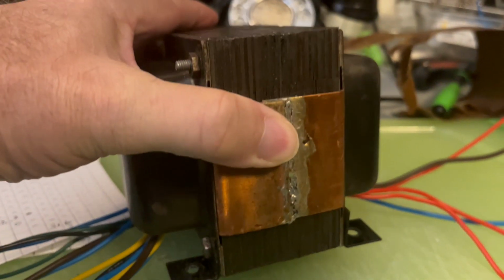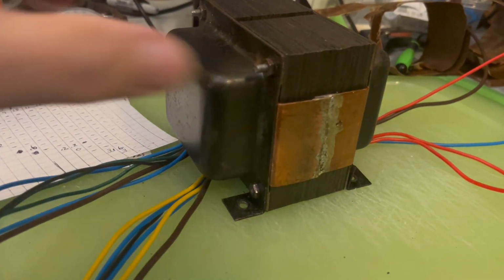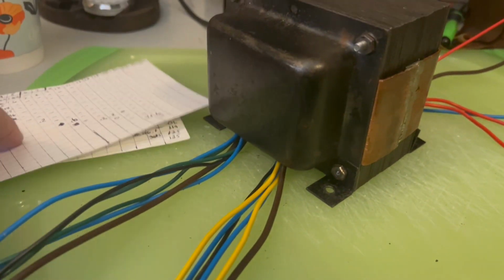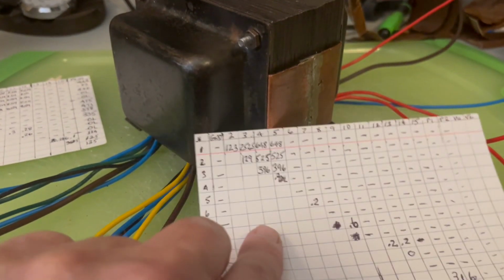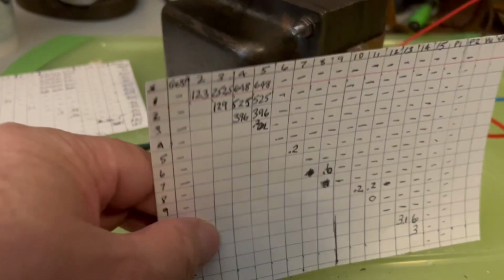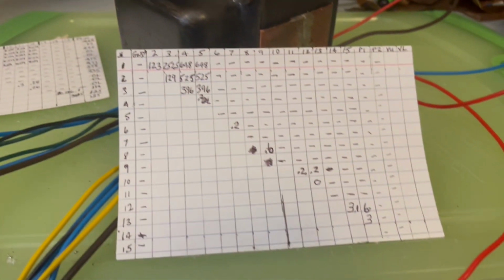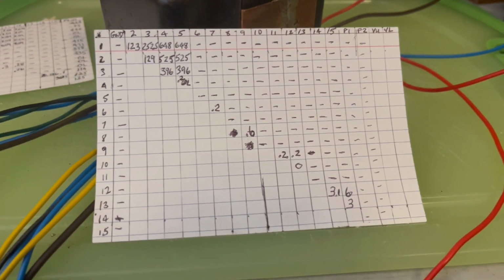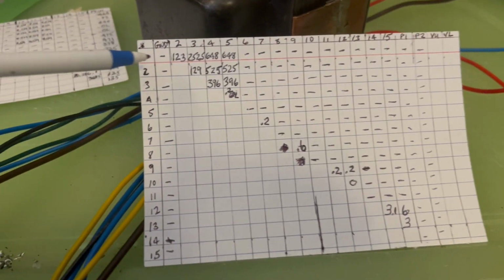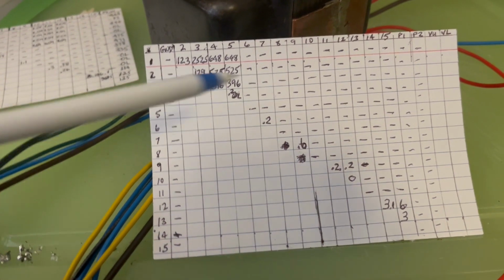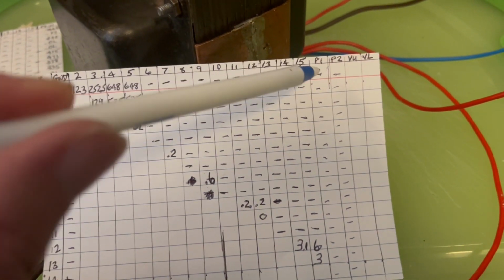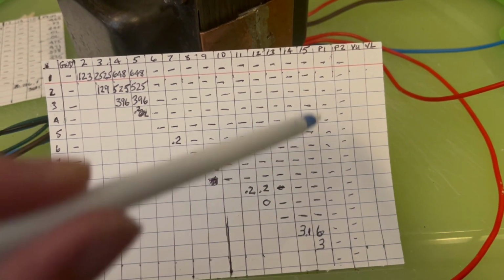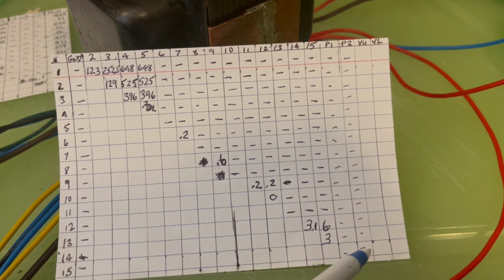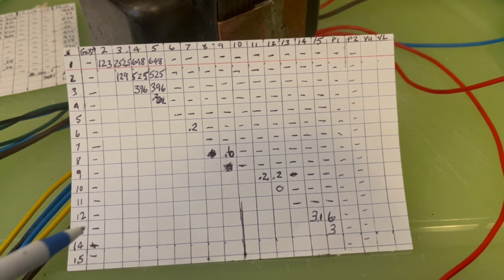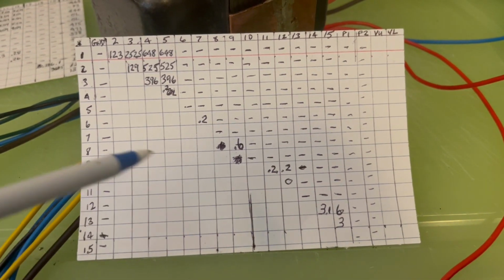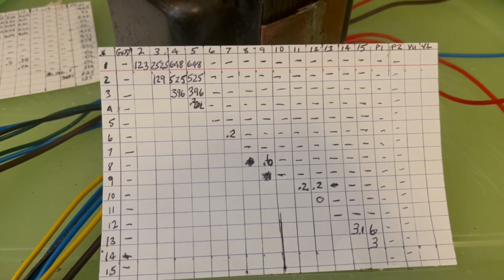I ran new leads for everything. I've gone through and rerun the test that I ran at the very beginning of this thing. It came out pretty good this time. These are measurements against ground. None of the leads were grounded. These over here are all of the secondaries against the primary. And I did compare the primary against ground. I just don't have any place to put it on this.